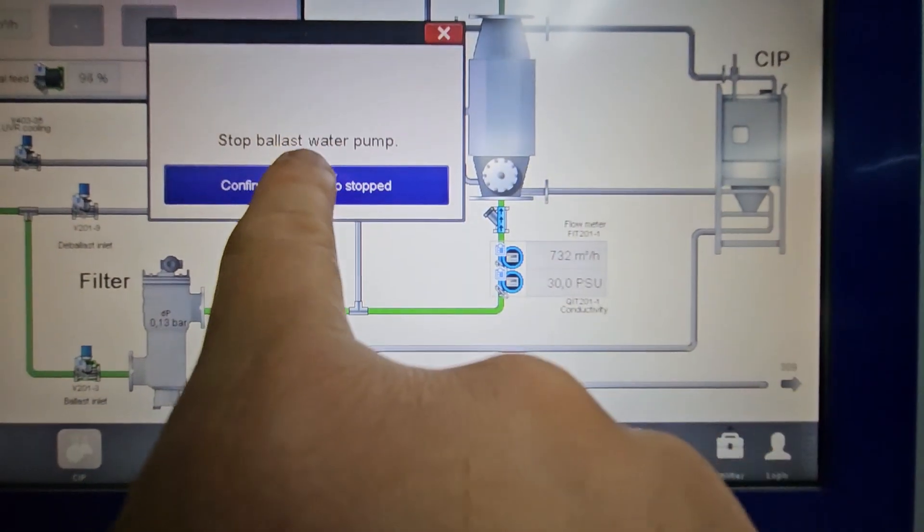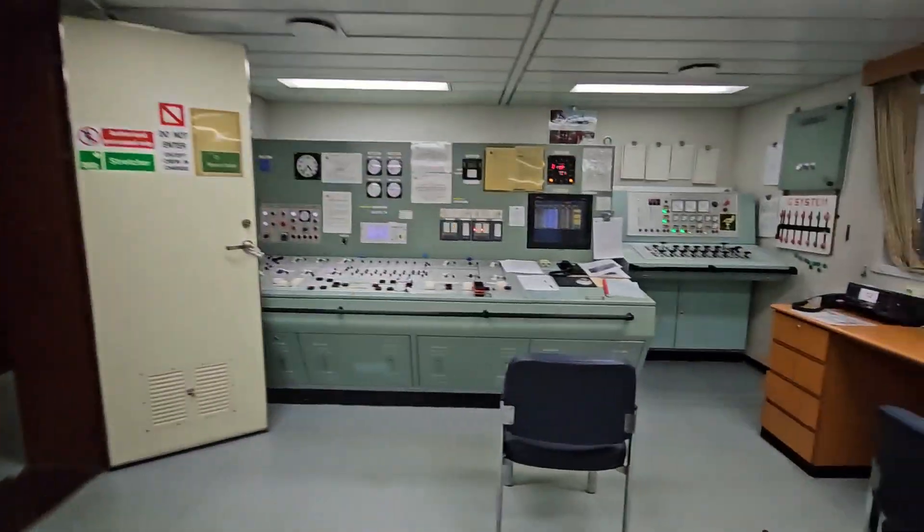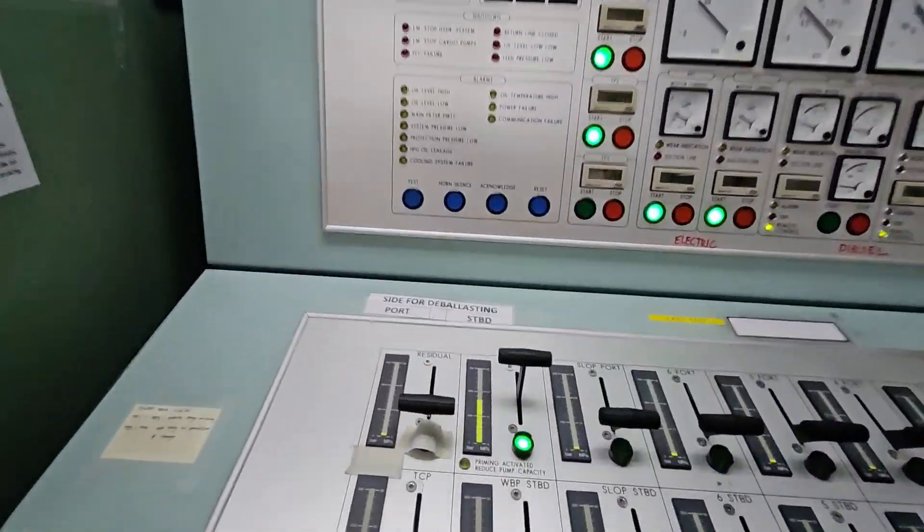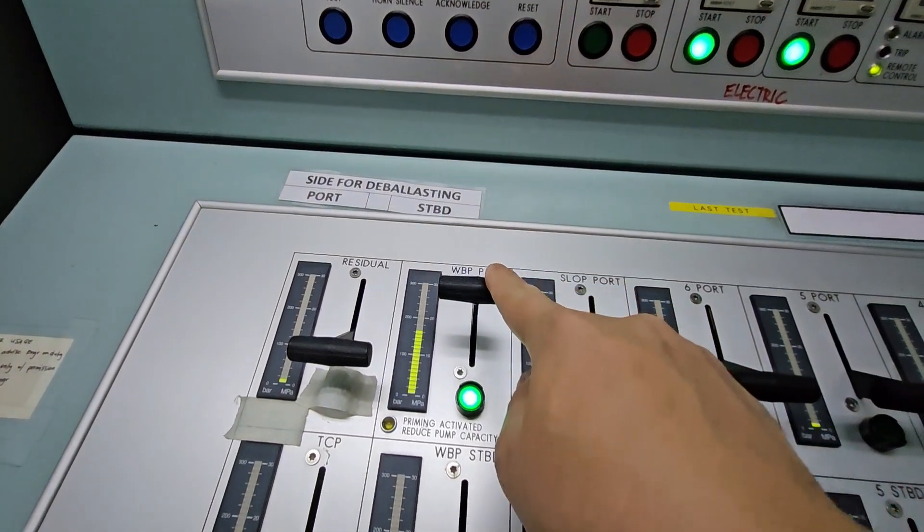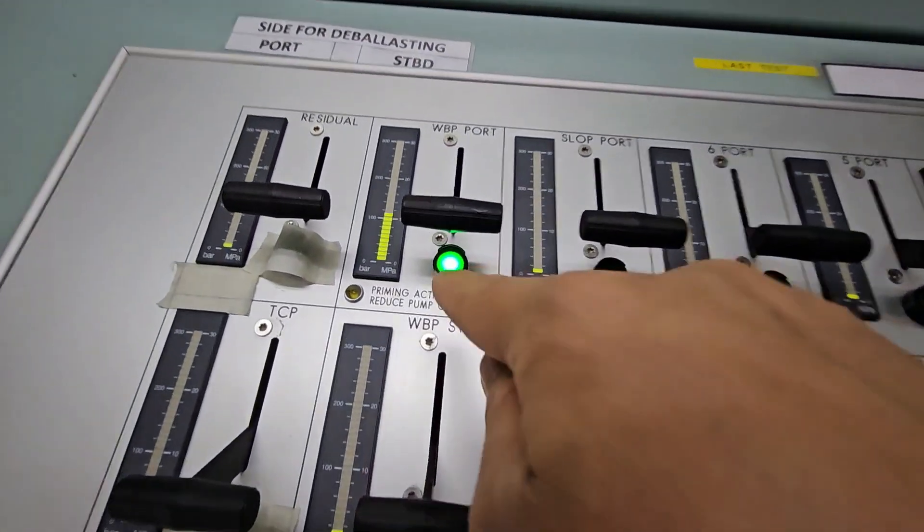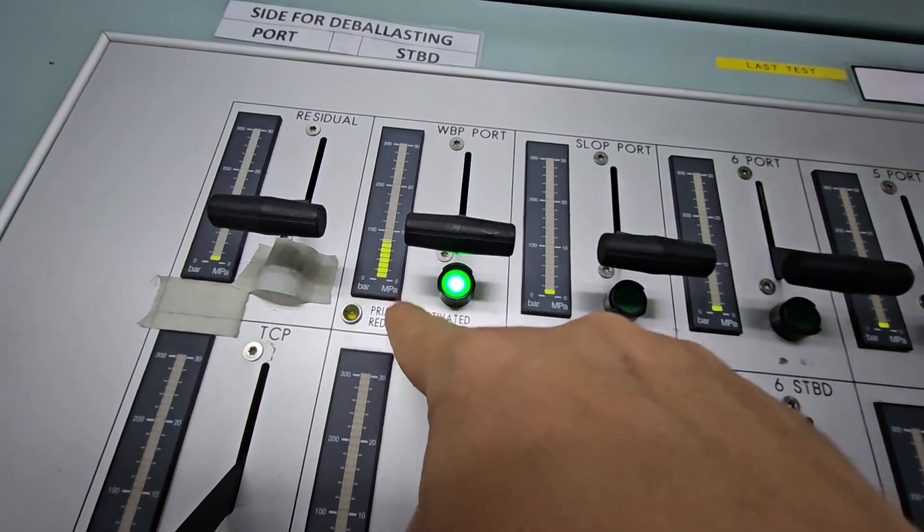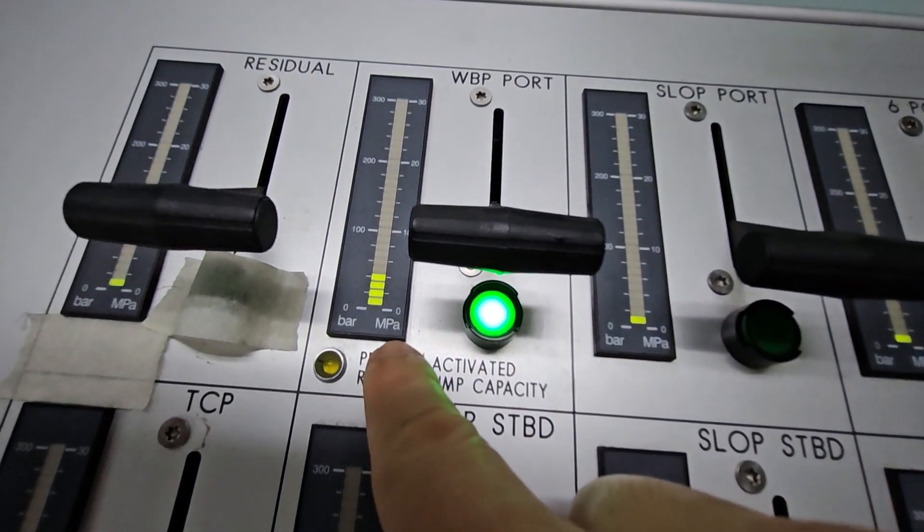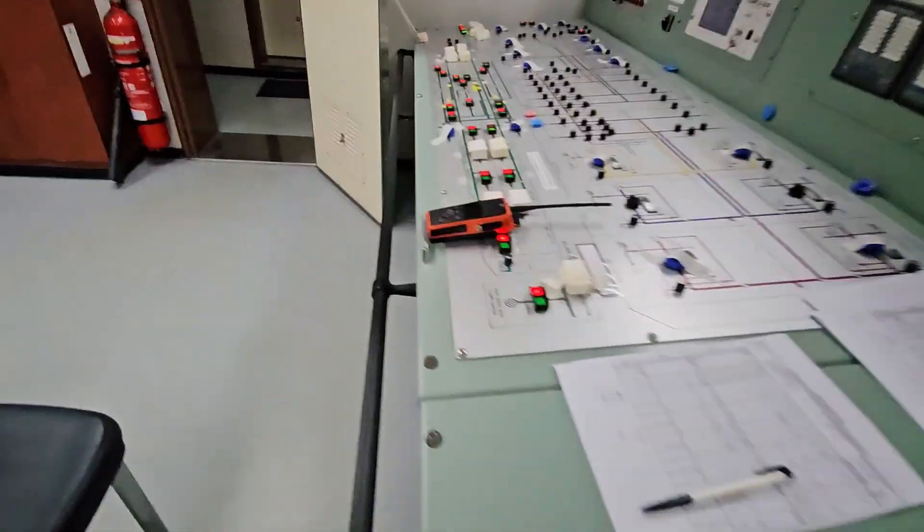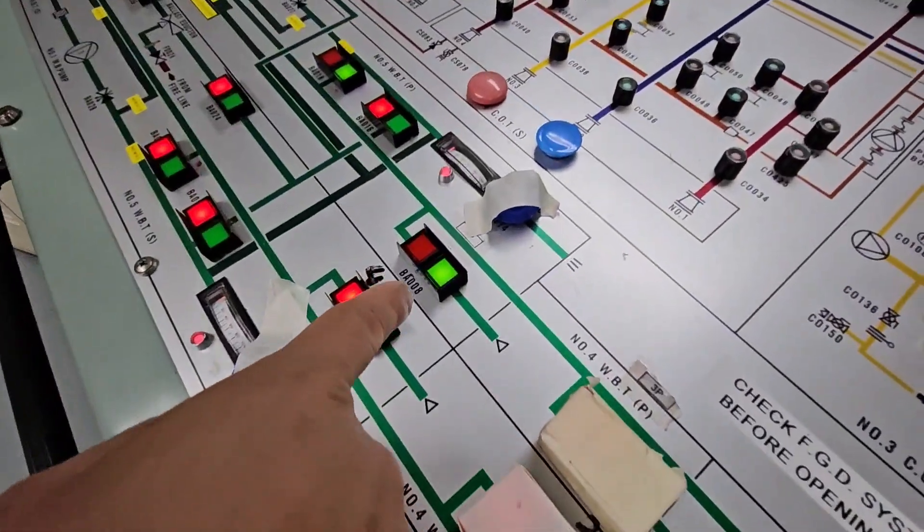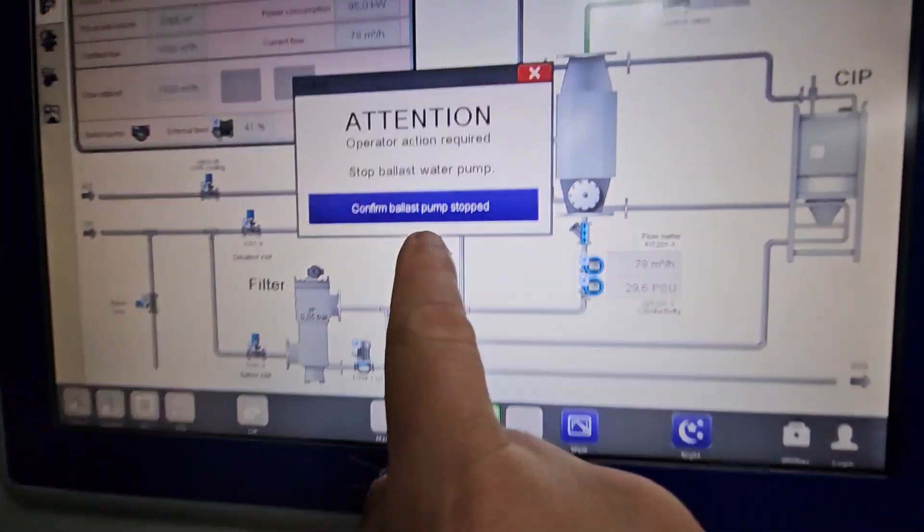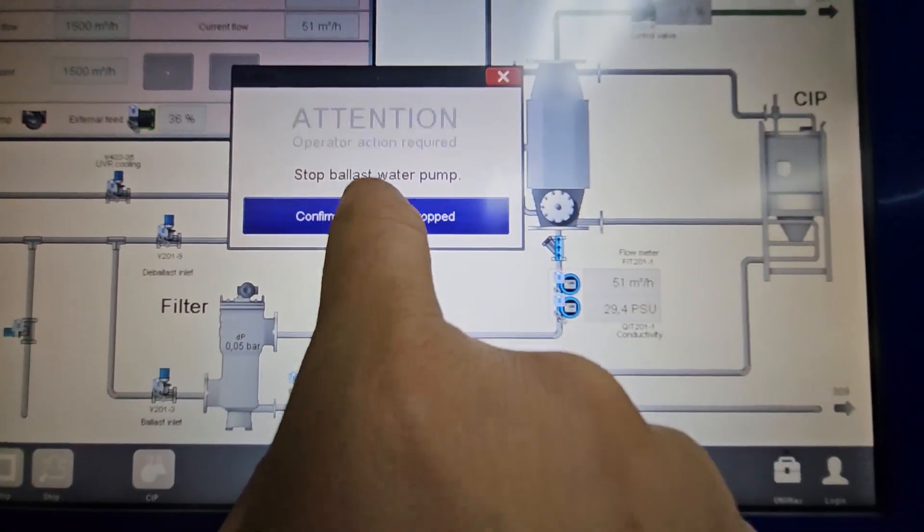There you go. Stop ballast water pump. So let's go stop the ballast water pump. Let's pull this down. We're using the port pump. You can see the green light when it's done, when it is down to zero. Then we can close the valve later since there's still pressure, and confirm ballast pump stop.